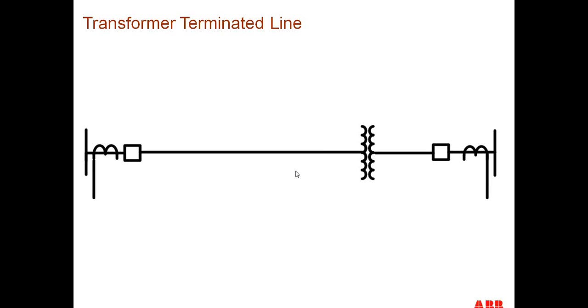Let's look at another one of our fine examples, and that's a transformer terminated line. Here we have a transmission line. The only difference is that instead of having a high side breaker, the line is terminated in a transformer with a low side breaker before we get to the relay. So the relay CTs are on the low side of the transformer, and on the remote end of the line, of course, between the breaker and the bus.